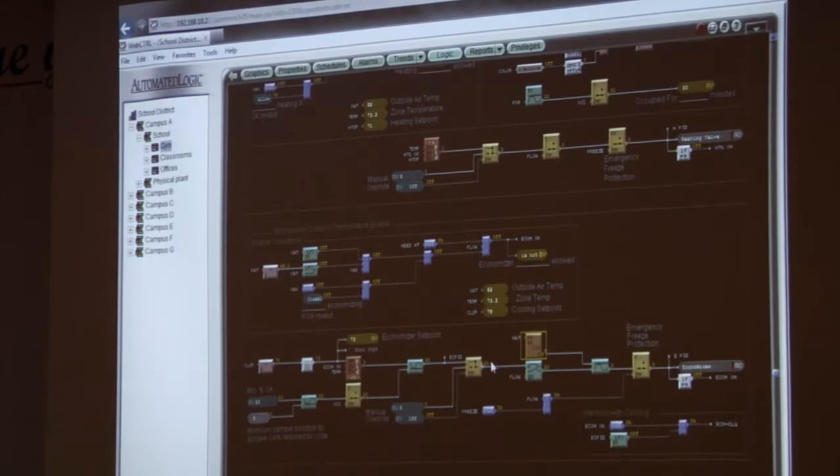All right, we come through here and I say, well, here, I could see this label. Now we're going to do something called chasing labels. Before, we used to have a wire that would go to every point, right? See the wire, see the wire, see the wire, right? It's going through. If we start taking these and start going to other sections, right, end up with wires all over the screen, right? It'd be very hard to follow. So ALC has given us these labels. Labels are just like wire nuts, right?